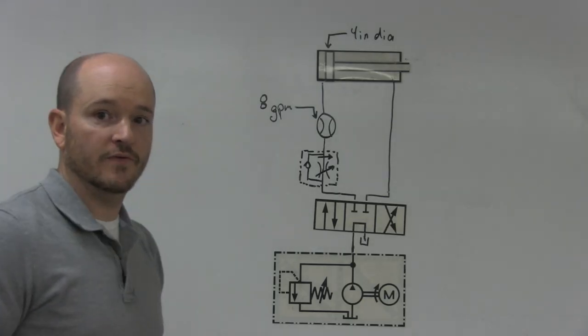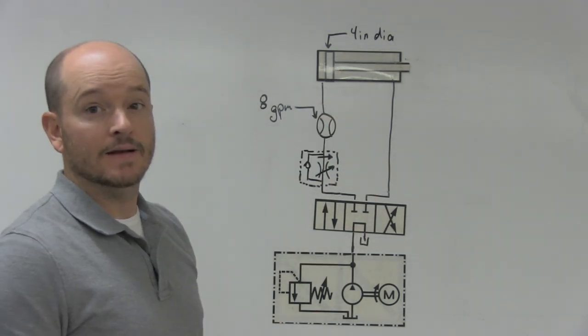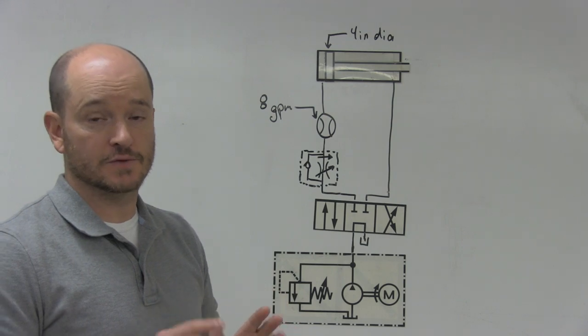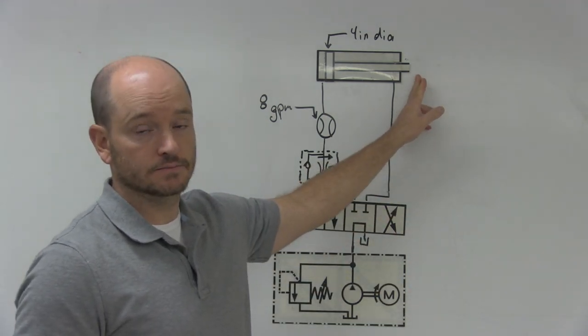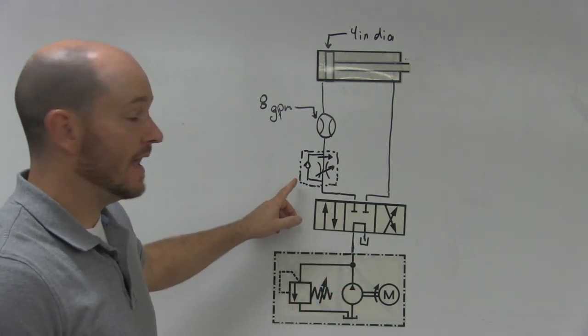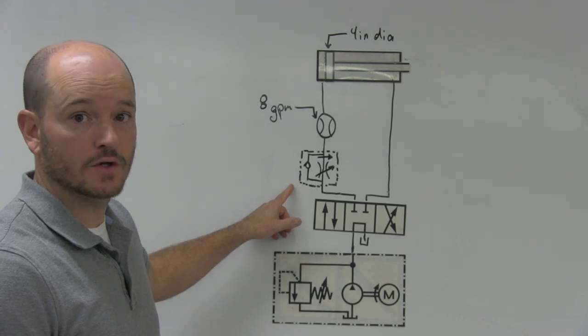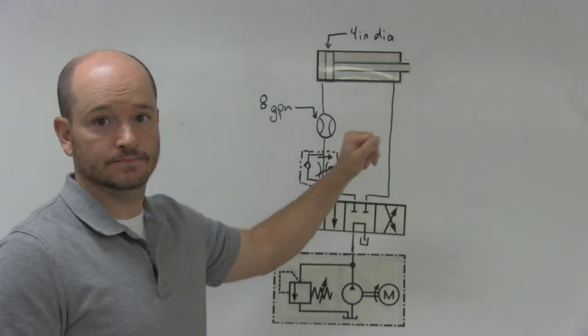In this video, we're going to focus on calculating the speed of a cylinder. Now we're going to start off with one of two assumptions. One, there's essentially no load on the cylinder. Or, if you have a varying load, that you have a pressure compensated flow control valve that will compensate for any variations in the load.